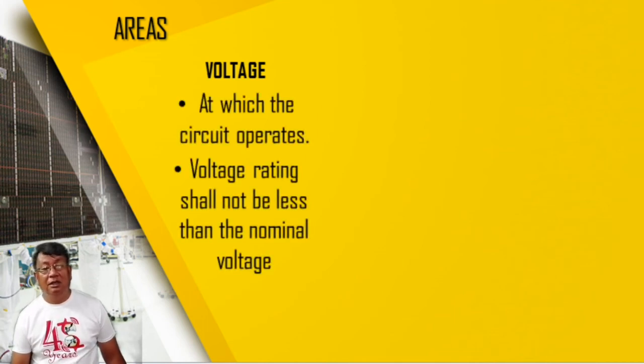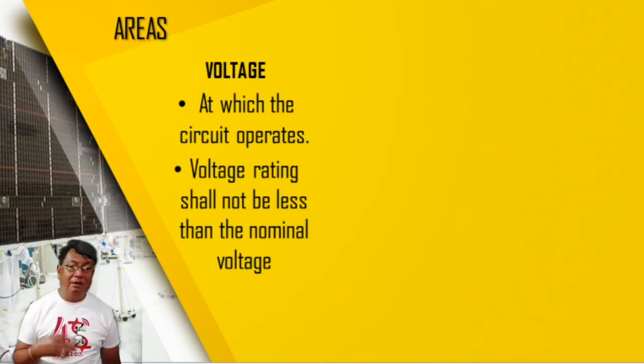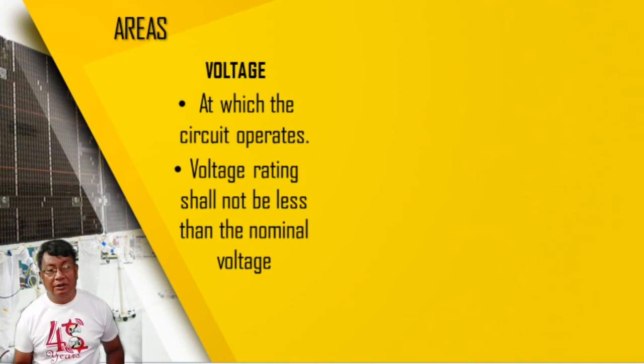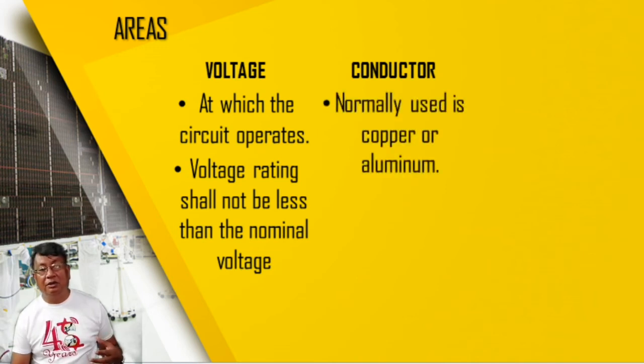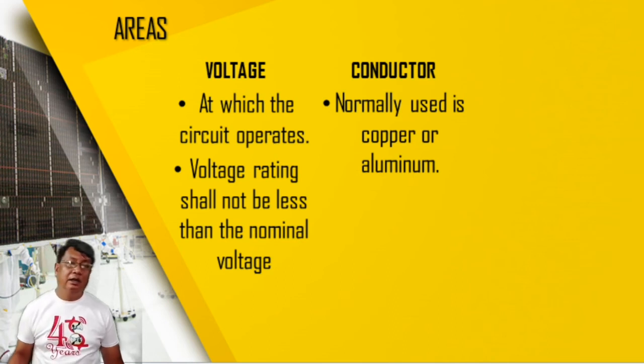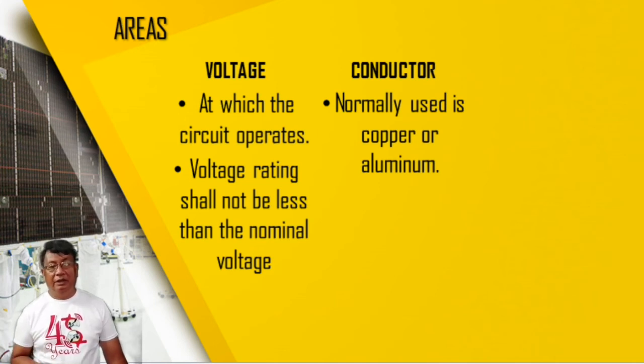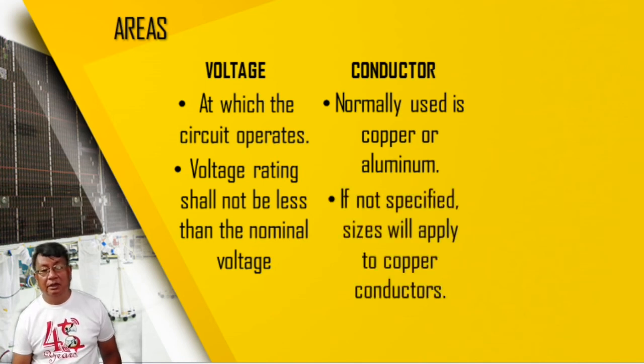So we have this voltage in which the circuit operates. What is the voltage? Operating voltage. Okay, sorry. Voltage rating shall not be less than the nominal voltage. Okay. So how about conductor? This conductor normally used is copper or aluminum. In the installation, generally we'll be using copper, but there are some conductors used in installation which are aluminum. But generally, most of the time in indoor installation, for example, we will be using copper. If not specified, sizes apply only to copper and copper-clad conductors. So other sizes may not apply unless specified.